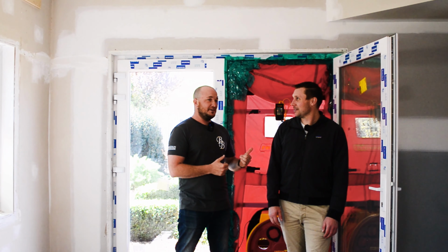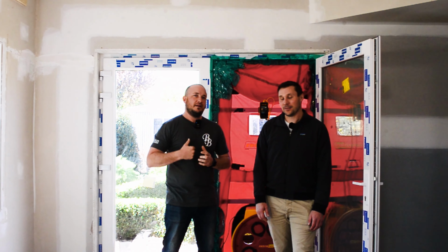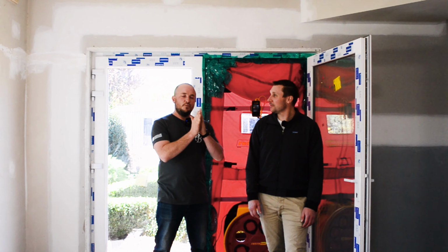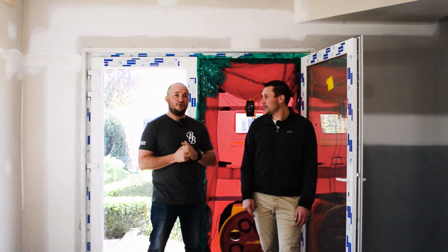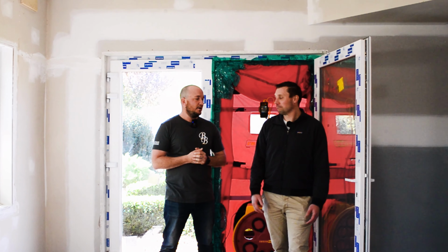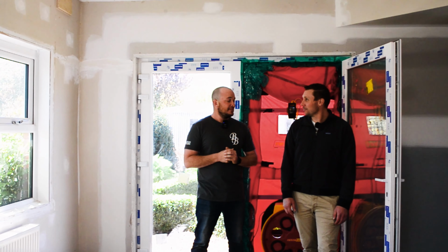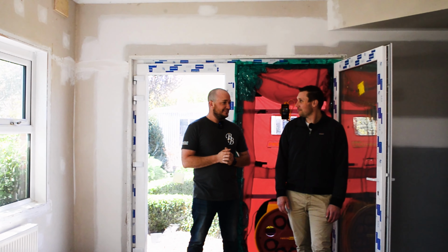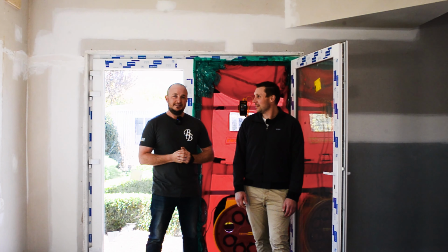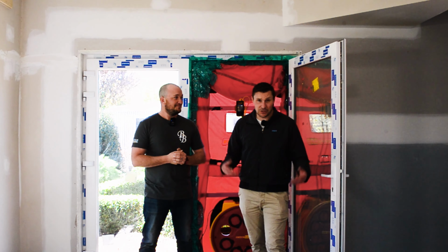And as Anthony mentioned, some of the challenges is we've got some of the old horsehair plaster here where we've had some windows retrofitted. So there's that almost hairline crack with the horsehair fibers where we've filled the windows, and that needed a little bit more work. Obviously an electrical box was a big one, and you just get onto it, but it's been awesome with the Outlier team, the client, and Backman Builders and our crew to achieve sub one air changes an hour on an existing home.